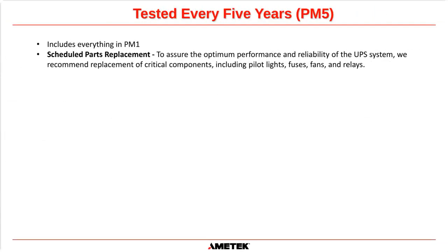And then that's all you have to do for the first 5 years of its life. And then on the 5th year, we would do a PM5, which includes everything in the PM1, but there are more parts that need to be replaced. And the most obvious of those will be the fans. The fans will need to be replaced. I think we replace all relays at the 5-year mark, and we also replace fuses as well. So at the 5-year point, it's fans, fuses, relays, and pilot lights. But everything else that we do in a PM1 is still performed.